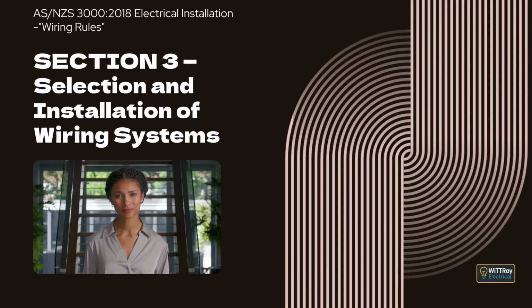Clause 3.11.4.2, Unenclosed. This clause explains that where Category A or Category B wiring systems use cables that are not installed in a wiring enclosure, the cables must be laid on a bed of sand or friable soil that is free from sharp stones. The bedding must be at least 50 mm thick, and the cables must then be covered with at least 50 mm of the same material before backfilling.